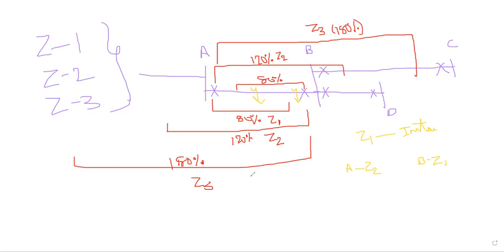So zone 1, I said instantaneous. Zone 2 is 350 milliseconds. This is the setting for zone 2. And zone 3 is 800 milliseconds. This is the setting for zone 3. 350 and 800. Means for the A breaker, zone 2, the relay will operate after 350 milliseconds. But this breaker will operate instantaneously.